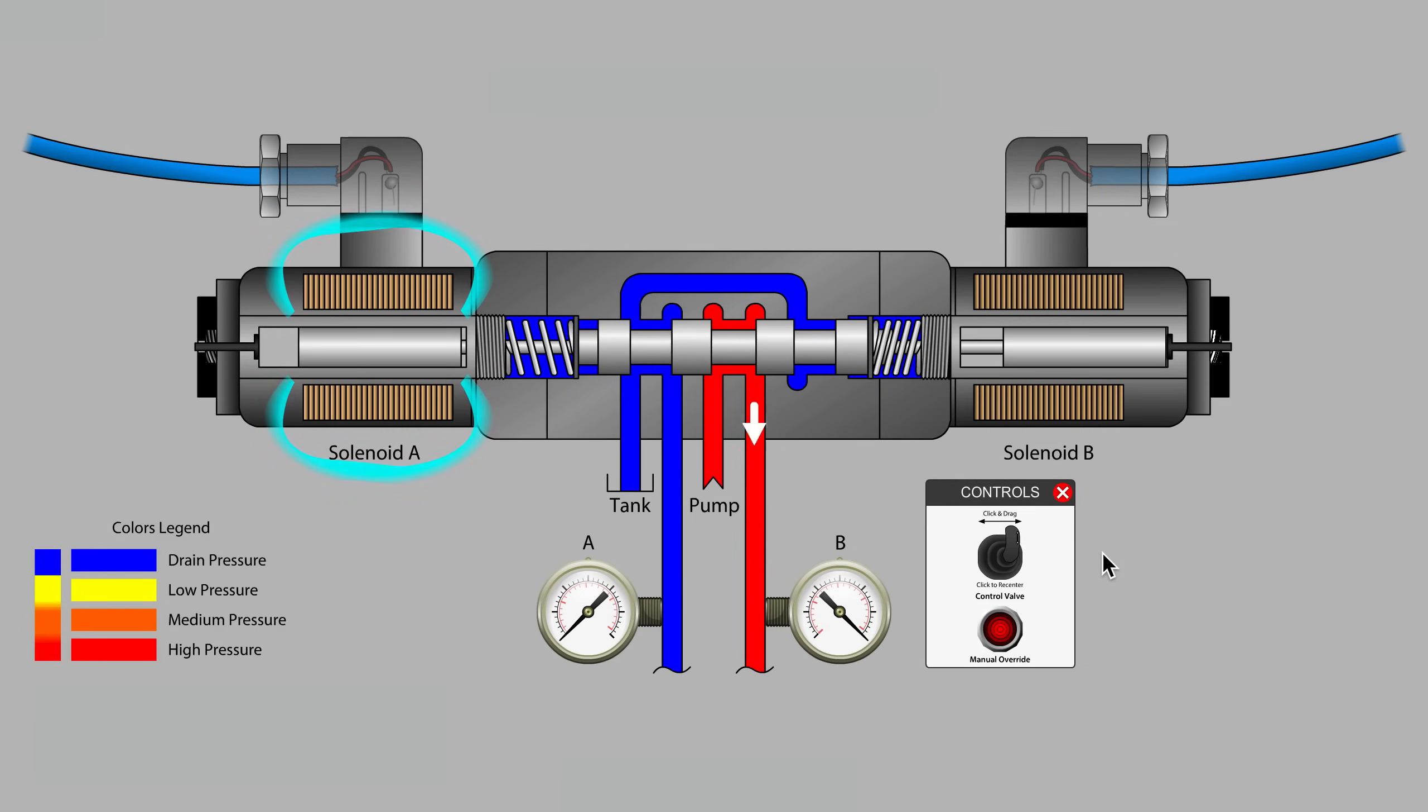When the valve is returned to neutral, notice that the gap between the pushpin and spool is now on the right-hand side. Whichever side of the valve has the pushpin gap has a slight force advantage when that solenoid is next energized.